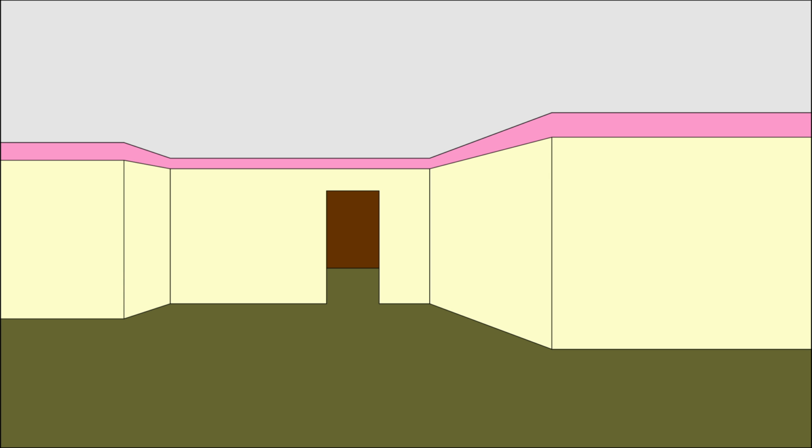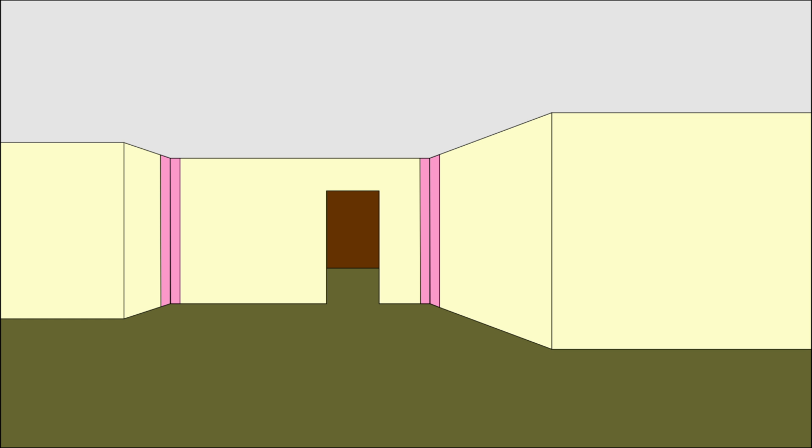Now the next one is the 150mm from the corner of a wall, or basically where two walls or partitions meet. So again, shown in pink here, we've got those two vertical zones there, and again they're 150mm from the corner, and of course it goes along both of the walls, so quite a wide section there to install cables and things. And again, this is between the corners or joints between walls, wherever they happen to be.